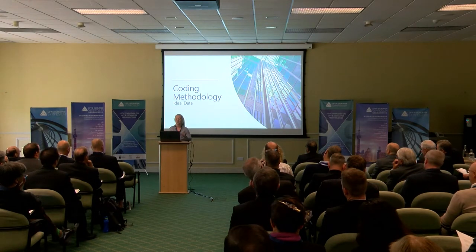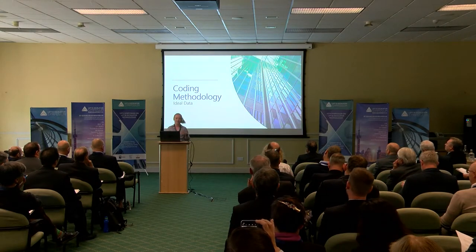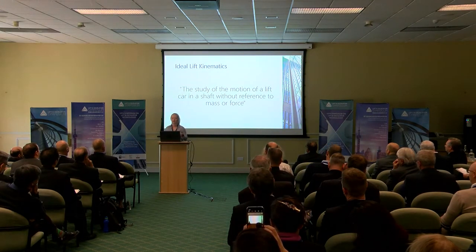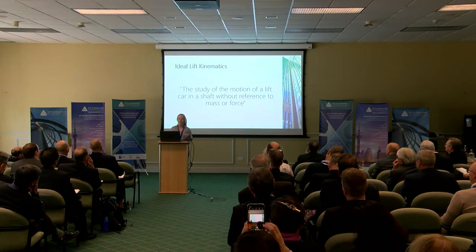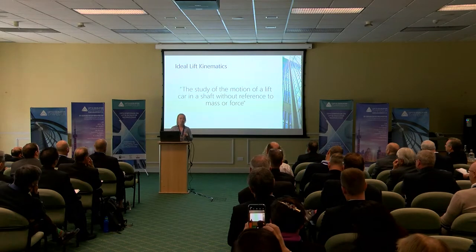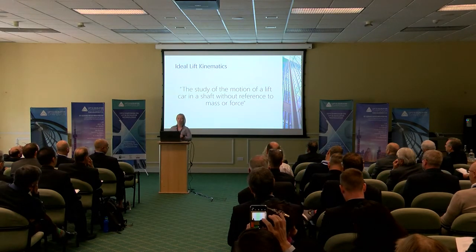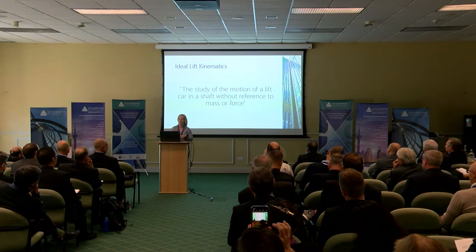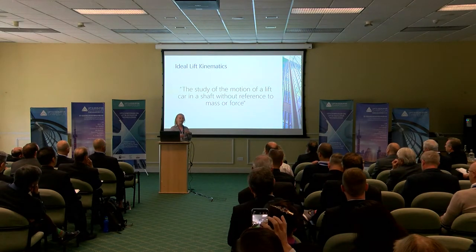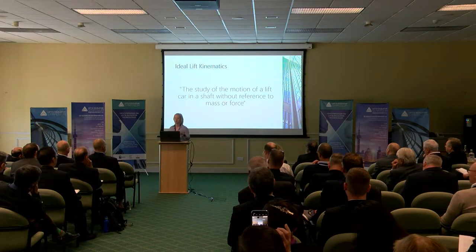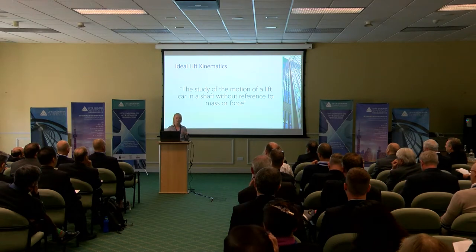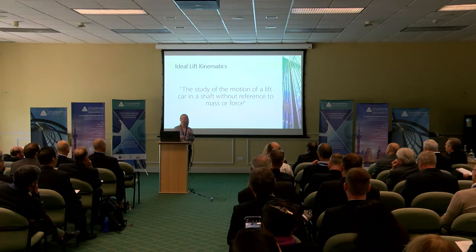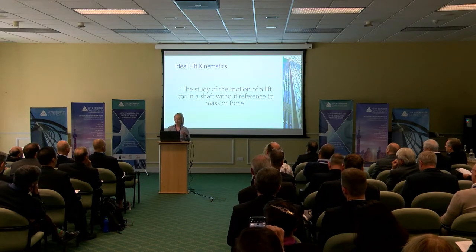Now for the fun part — I'll briefly cover the methods I took to create this software. I want to begin by introducing a key concept that played a major role in the development: ideal lift kinematics. This is defined as the study of the motion of a lift car in a shaft without reference to mass or force. For passenger-carrying lifts, there are limits on the maximum values of jerk and acceleration, defined by what a human perceives as comfortable. Ideal lift kinematics takes this human comfort criteria into consideration, and from that it has become possible to derive equations representing this ideal motion. These equations can be plotted as continuous functions representing the optimum displacement, velocity, acceleration, and jerk profiles of a lift.